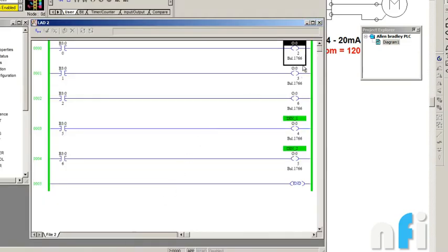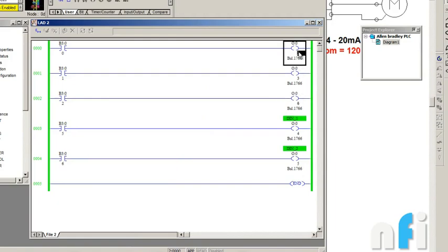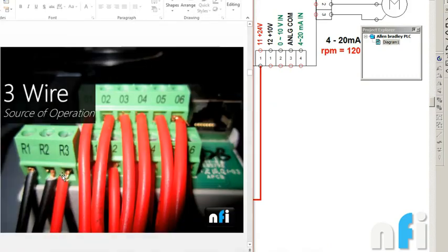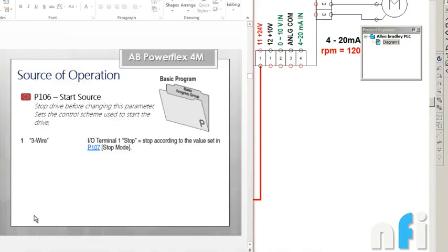To make it easy, I have this logic here. It says 0, 2, and 6 - we have three outputs. Now the first thing is we have to first enter the parameter in the VFD. This was three-wire. Let's see what are the parameters. Parameter 106 again, start source, the same parameter in which we have to enter one.